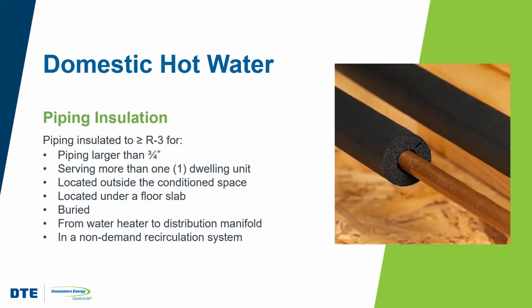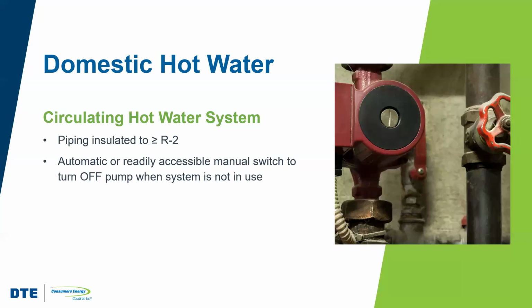This is also required if the system is serving a continuously circulating recirculation system. But if that recirculation system is a demand-based system, meaning it only operates when it's necessary, then the domestic hot water piping only needs to be insulated to R2.